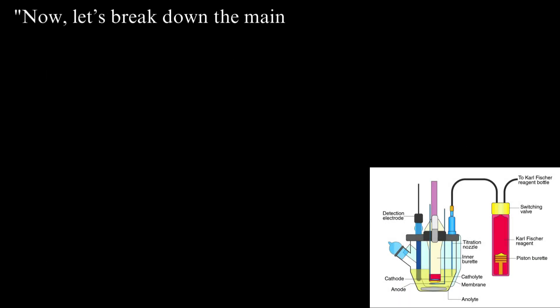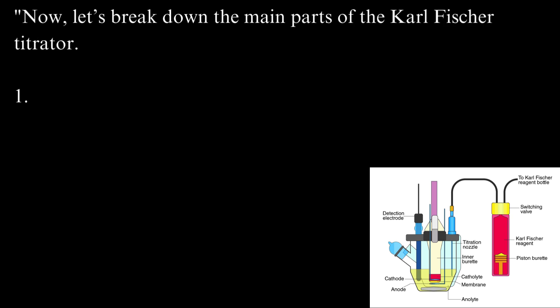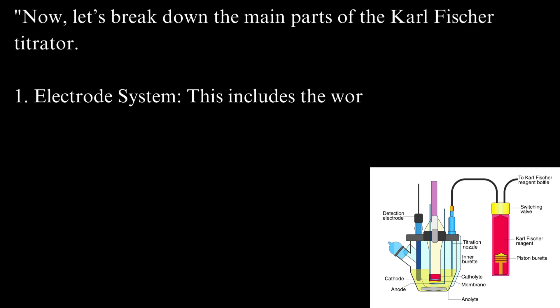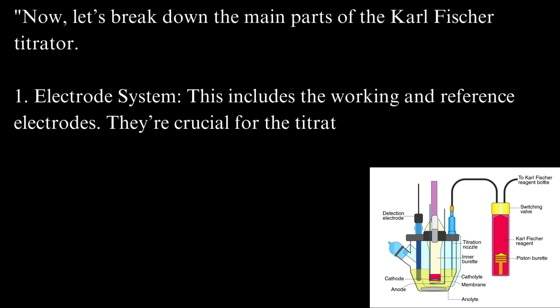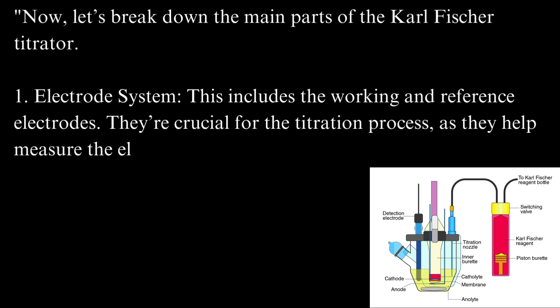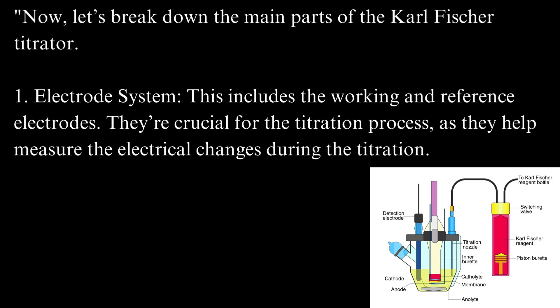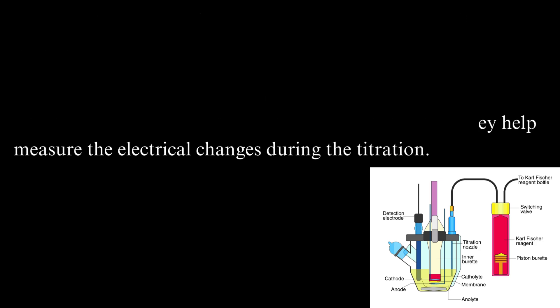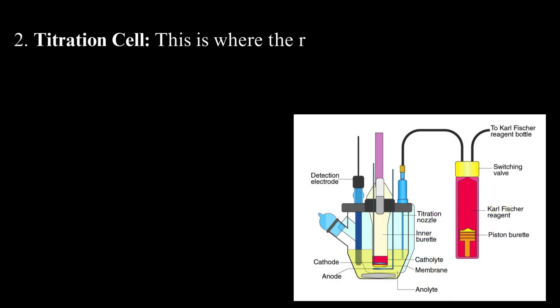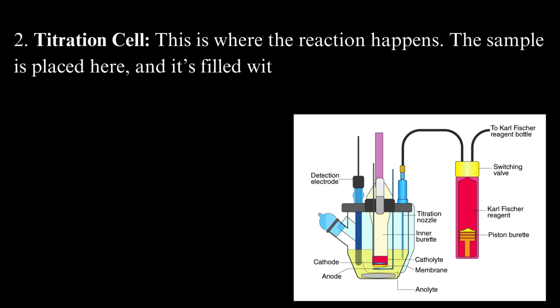Now let's break down the main parts of the Karl Fischer titrator. Electrode system: this includes the working and reference electrodes. They're crucial for the titration process, as they help measure the electrical changes during titration. Titration cell: this is where the reaction happens. The sample is placed here and it's filled with the Karl Fischer reagent.